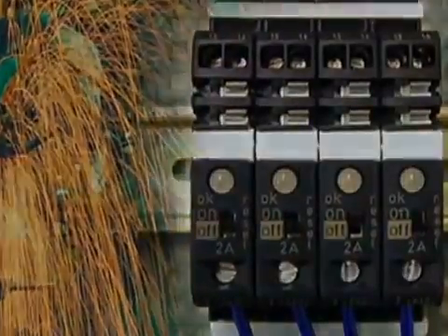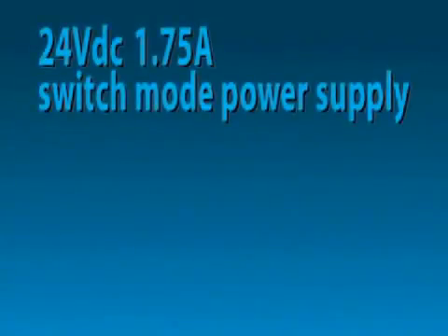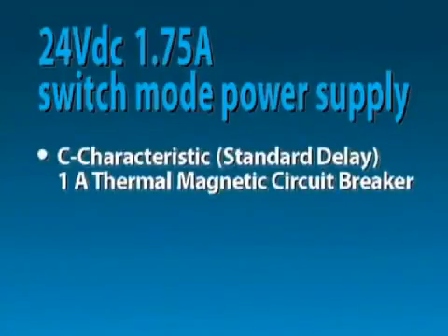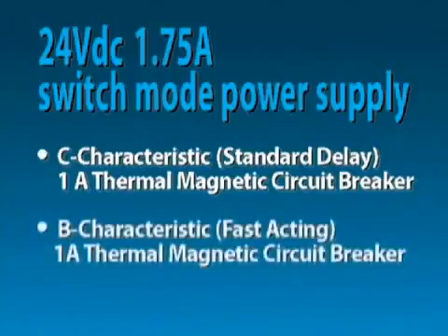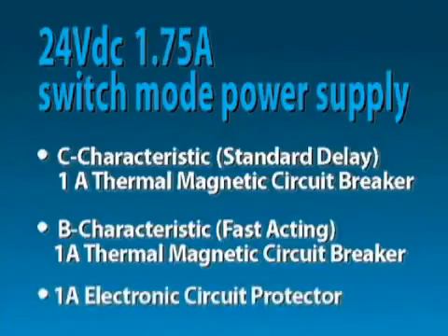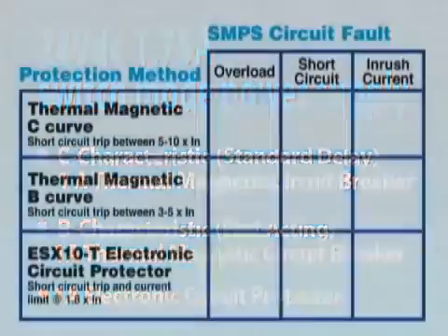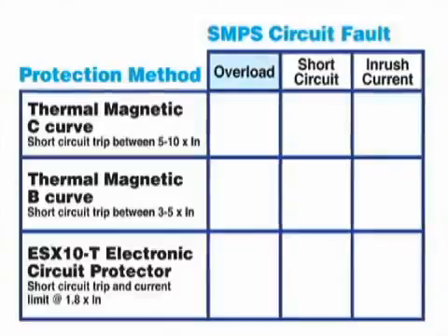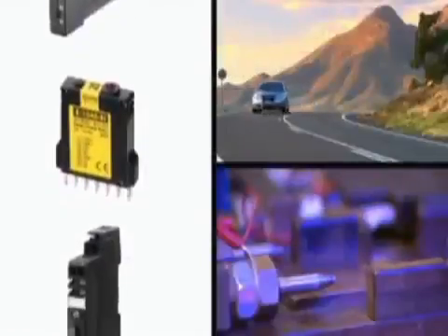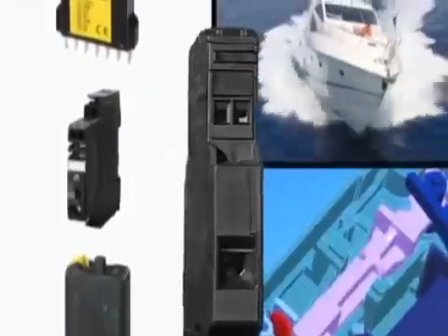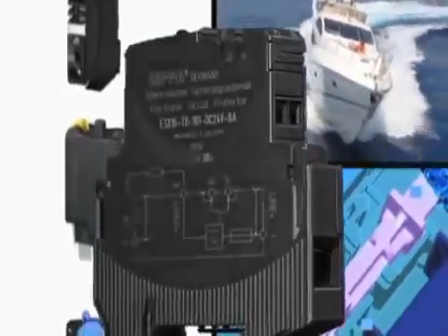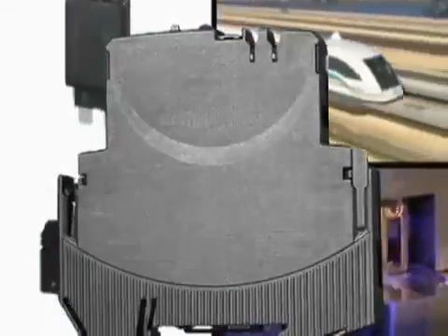We'll demonstrate this innovative technology using a 24-volt DC 1.75 amp switch mode power supply, a C characteristic standard delay 1 amp thermal magnetic circuit breaker, a B characteristic fast acting 1 amp thermal magnetic circuit breaker, and a 1 amp electronic circuit protector. We'll simulate 3 real-world conditions: an overload condition, a short circuit condition, and a startup high inrush current condition. You'll see the function and benefits of using ETA electronic circuit protection against these conditions compared to any thermal magnetic circuit breaker widely used today.